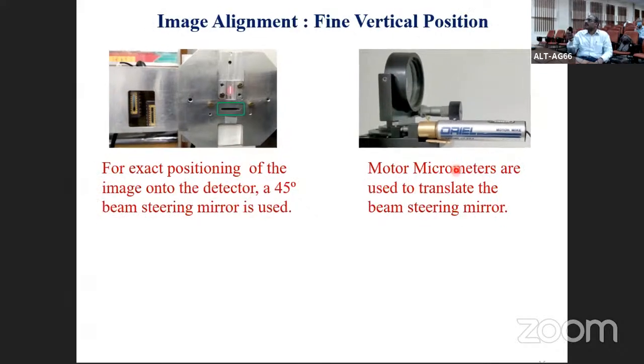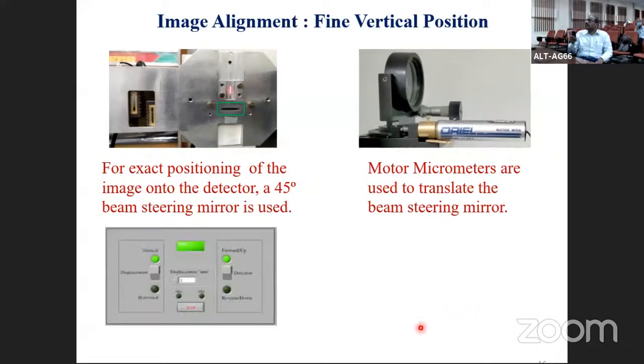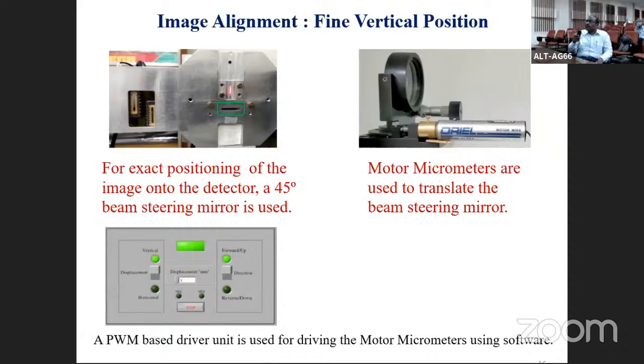accomplished by driving this motor micrometer in a certain fashion, like you use up-down motion to translate the image up and down, and use another one to translate the image in the horizontal direction. In the first case, you just go in a step. You can decide what step you want, a displacement like 1 millimeter or 2 millimeter. You decide the vertical displacement, and whether up or down. These are the choices given to you. So you keep on moving it in one direction and look for the transition of the image, the moment it hits one of these detectors.